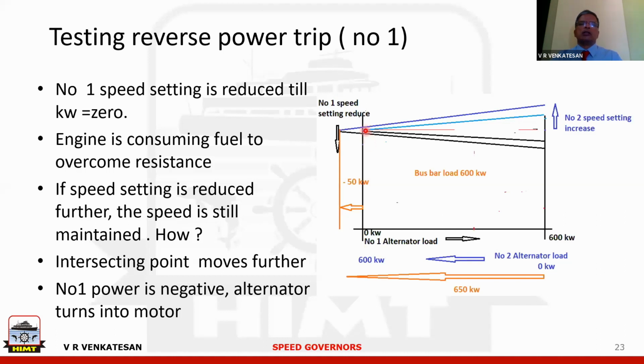So for example, if you think that at this point, with 0 electrical power, 100 kilowatt is required for overcoming friction, then here what is happening is minus 50 is the power. That means out of this 100 kilowatt which is required to overcome friction, 50 is still coming from the engine, but 50 has to come from the other generator. So we say number 1 power has become negative, or your alternator has turned into a motor. This is a condition we always call motoring. Motoring means your alternator is drawing electrical power and it is producing mechanical power.